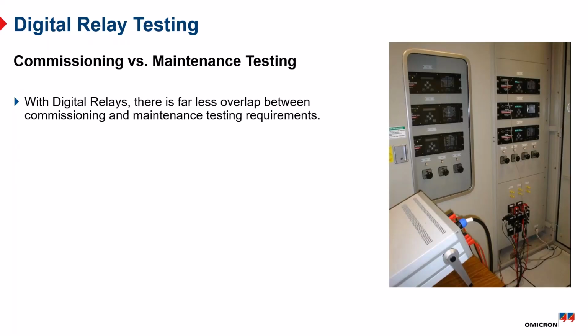Commissioning versus maintenance testing for digital relays is also different, because once a relay is commissioned, the settings haven't really changed, and it is self-diagnostic to monitor for a lot of this stuff. So you don't have to do quite as much testing on the routine side. But the commissioning testing, because what used to be hardwired in the panel, electromechanical relays, with panel switches and putting relays in series or whatever to construct your logic with hard wires, now is done inside the box. So the commissioning task on digital relays is a bit more complex and a bit more time consuming. So those are the kind of considerations that really should be taken into account.